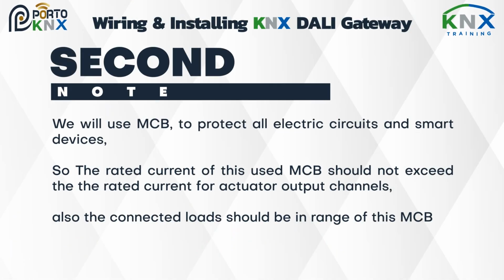Second note, we will use MCB to protect all electric circuits and smart devices, so the rated current of this used MCB should not exceed the rated current for actuator output channels. Also, the connected loads should be in range of this MCB.